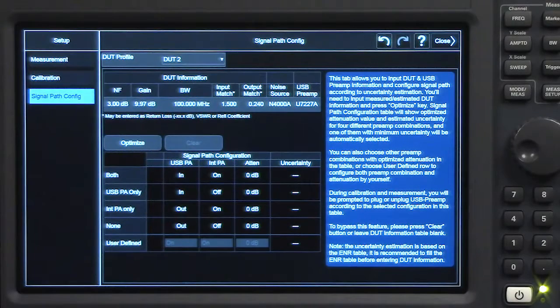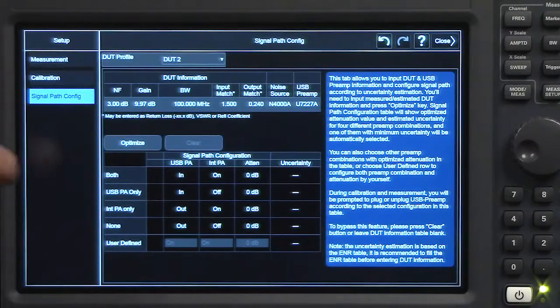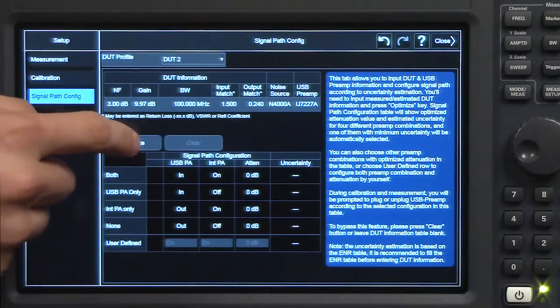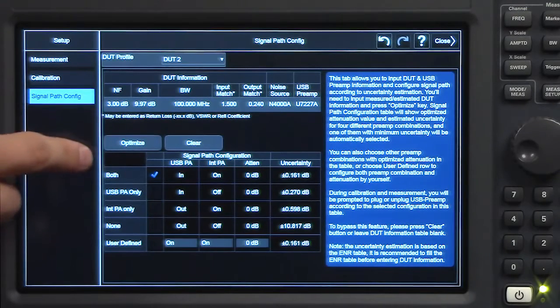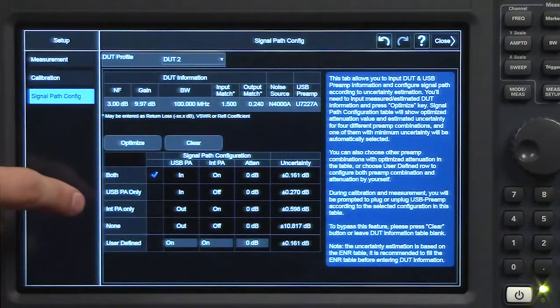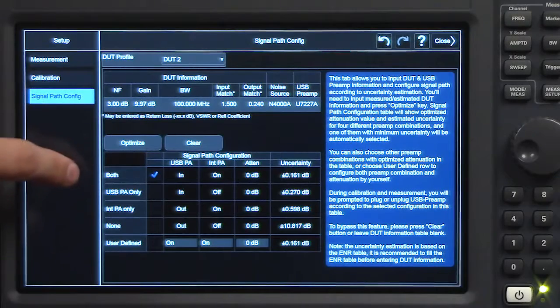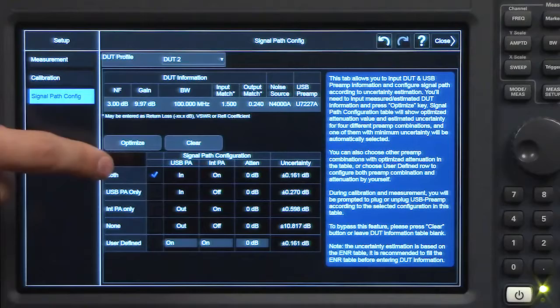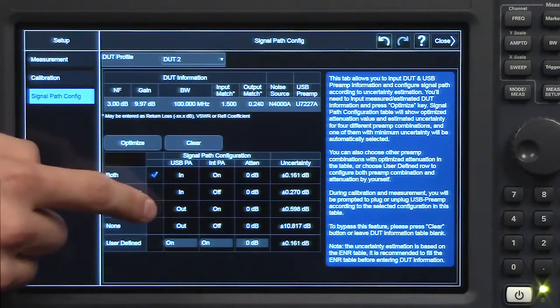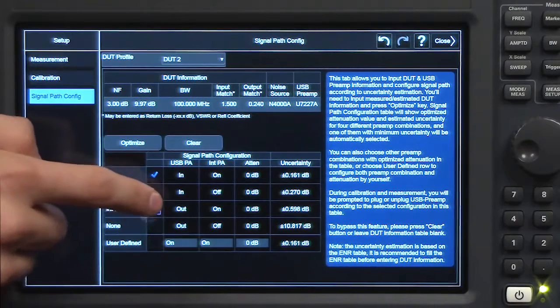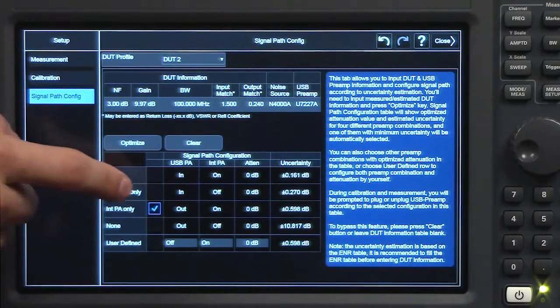I've already put in hypothetical information for a DUT. If you go ahead and press optimize, it'll select the configuration of internal and external preamps which yields the lowest uncertainty. But I can manually override this and choose to do the internal preamp only if I wanted to.